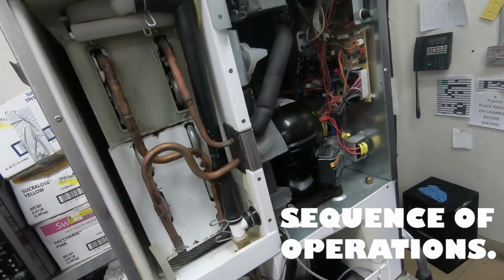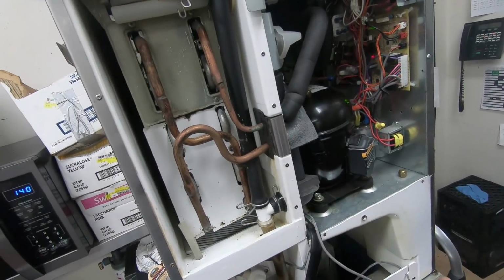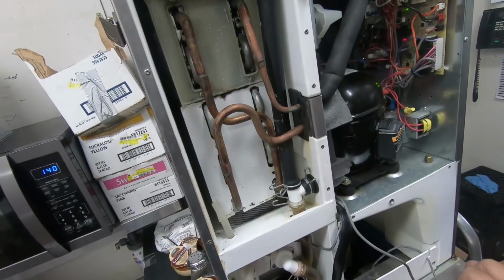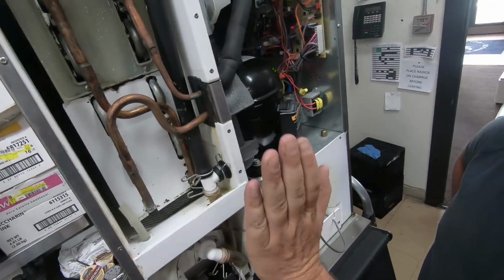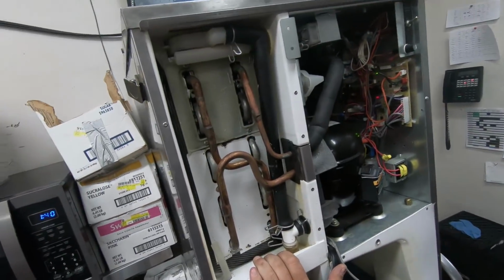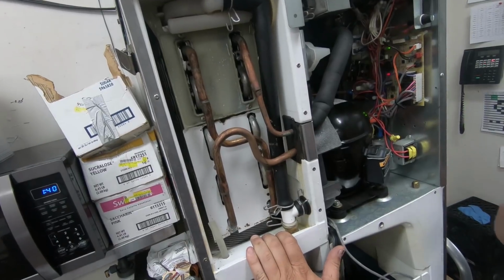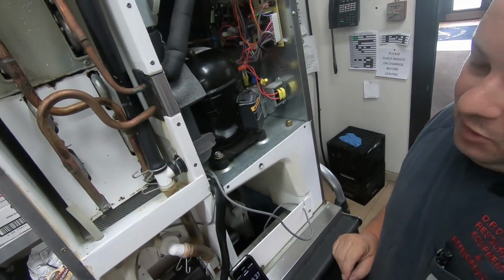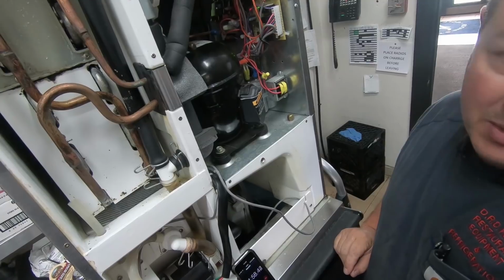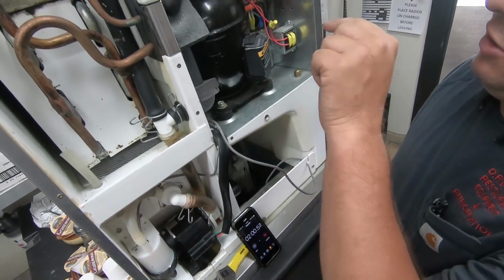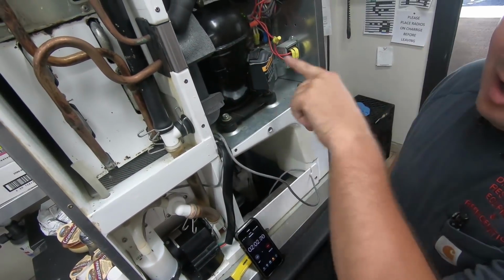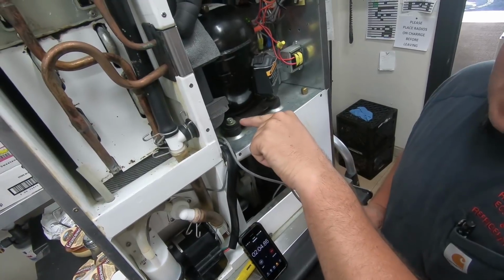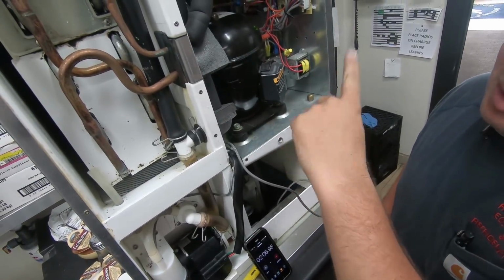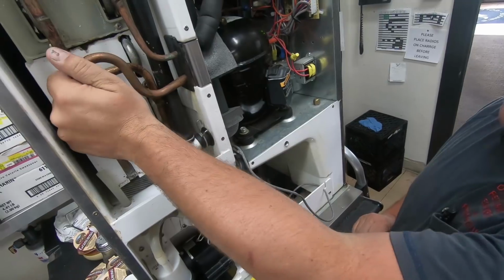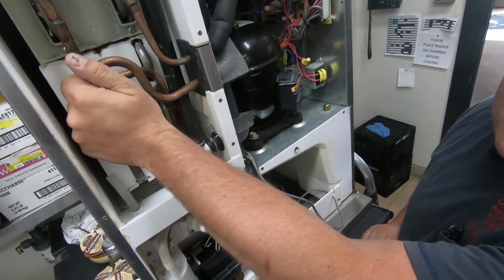Here on this machine, it's startup, a 5-second delay, then you go into a 60-second fill cycle, and it fills as long as the float switch satisfies within 60 seconds. It'll immediately launch into a harvest cycle. It always starts the harvest cycle. So when you start harvest cycle, right now you just got hot gas bypass running.